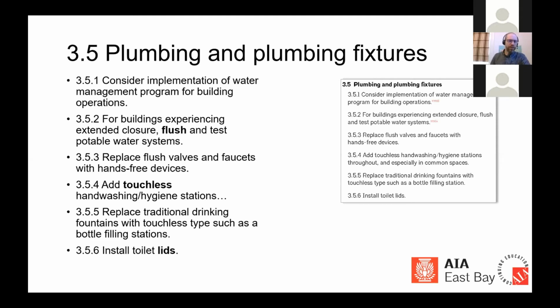And something that's in here on 3.5.2 that I want to point out, for buildings that have been closed for quite a number of weeks, the potable water system is something that does need to be flushed. We all know that the water in the United States is chlorinated, but how long is that chlorination effective? It does need to actually be moving through the system. That chlorination isn't effective forever, and there is a certain threshold, whether it's days or a number of weeks before reoccupying, beyond which the facility maintenance team could work to flush it out.